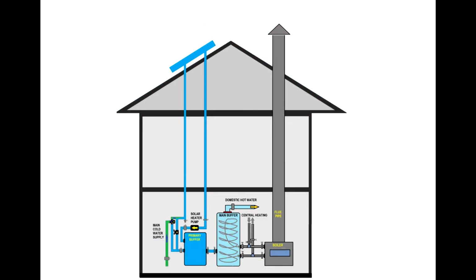Now, if you look at this system, it is a system which considers the volume of water consumed by a commercial environment like a store or a factory or whatever. This is a good system because it allows the main water supply to be heated and the energy to be stored in this primary buffer. And the boiler will have the capability to raise the temperature faster because the water will be preheated to 50 degrees Celsius.